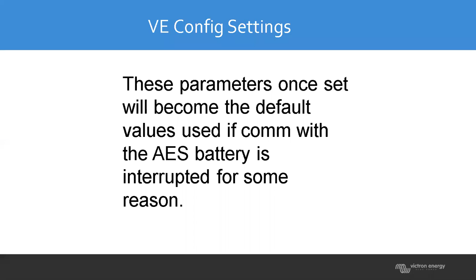So on the VE config, on the General tab, on either size battery, we'll want to enable the overruled by remote, enable battery monitor. The state of charge when finished is 95%. The total battery capacity is per battery installed. So 110 amp hour is what you would put in there if you had one battery, 220 if you had two, and so on. The 48 volt version that we have here, we've got two, so I've put 260 amp hours in there. And the charge efficiency for both is 95%.